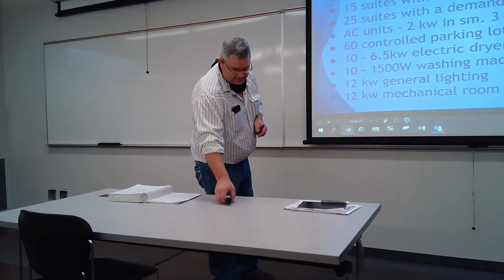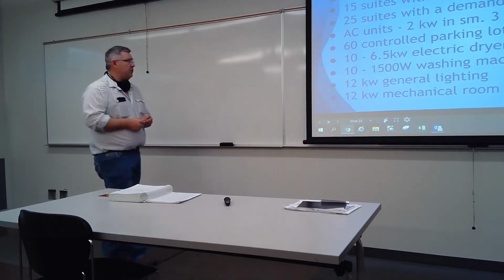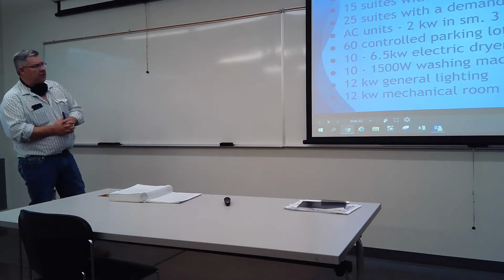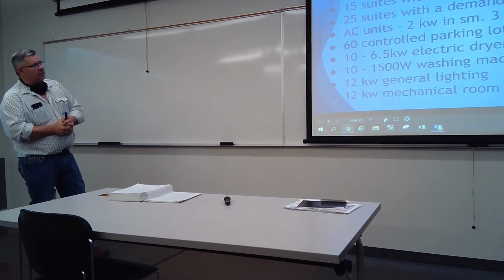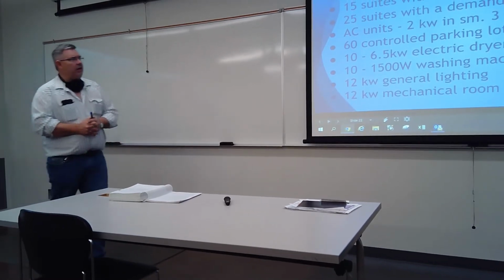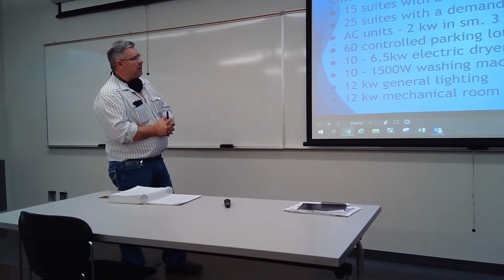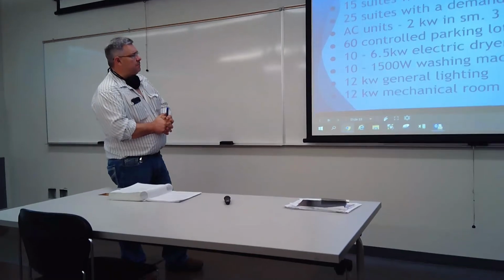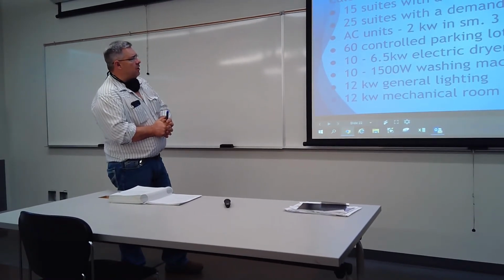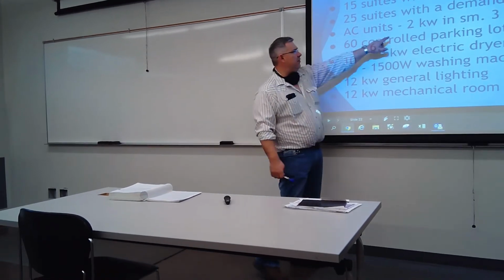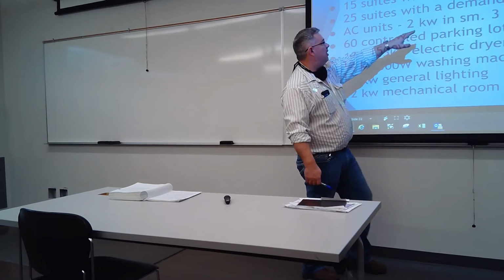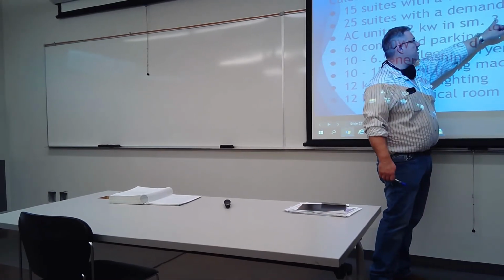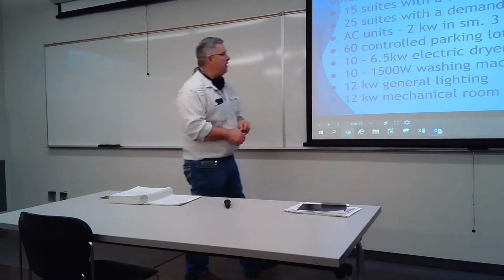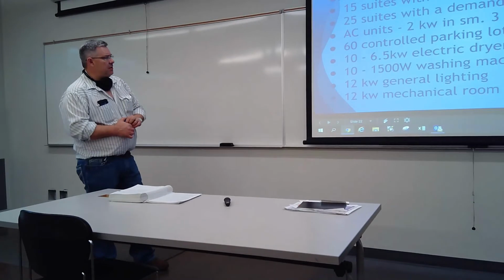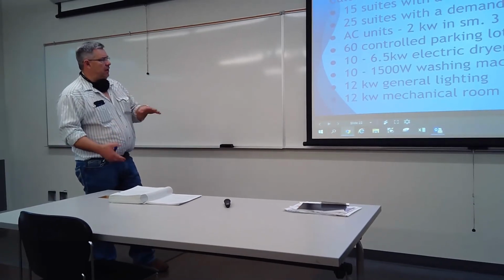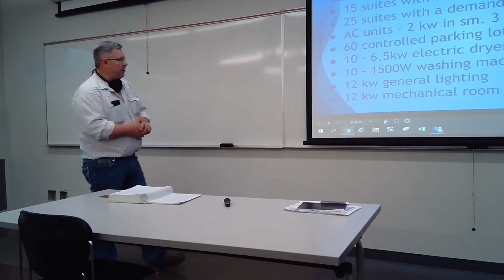So I guess the best thing to do is we're going to do a rundown here, and we'll do the actual calculation for this apartment. So we've got 15 suites that have a demand of 20 kilowatts each. We've got 25 suites that each have a demand of 16 kilowatts. All of the smaller units, the 16 kilowatt units, have a 2 kilowatt air conditioner. The bigger units, which obviously are the ones with the higher demand, each have a 3 kilowatt air conditioner in them.